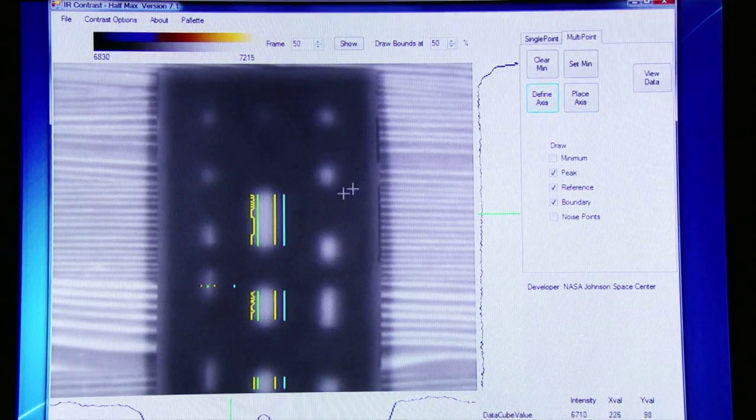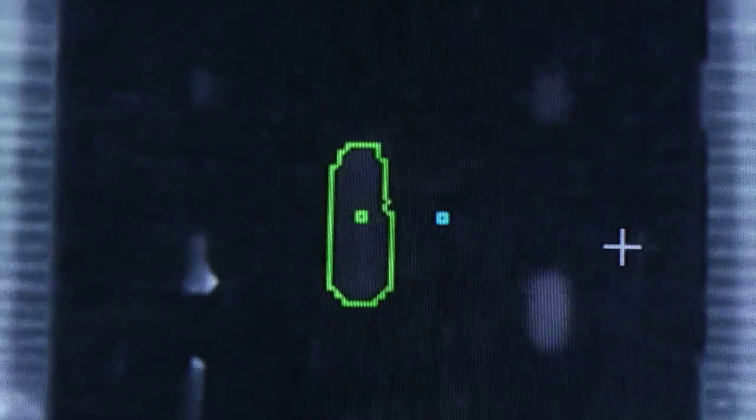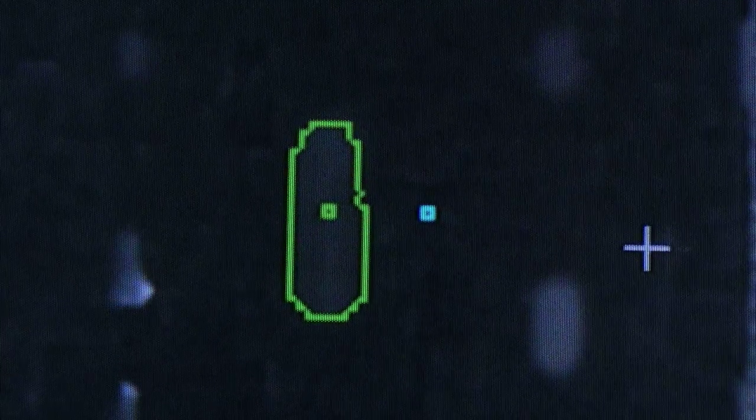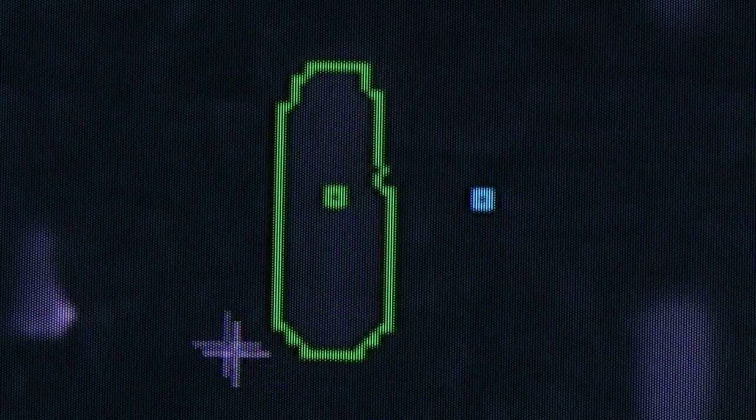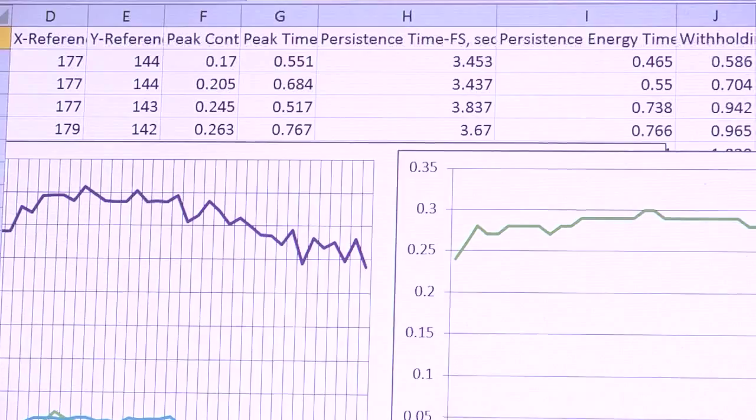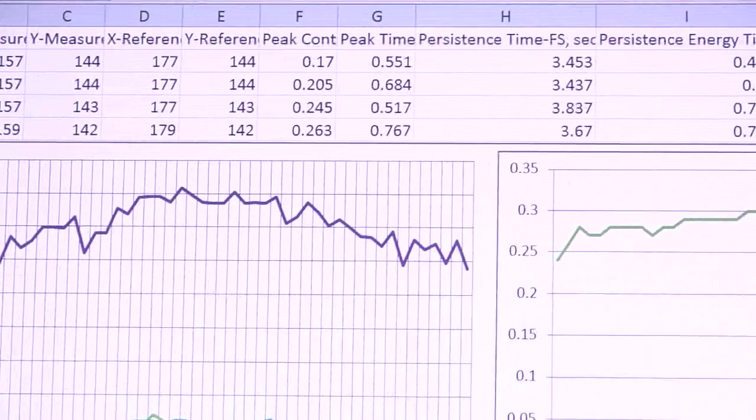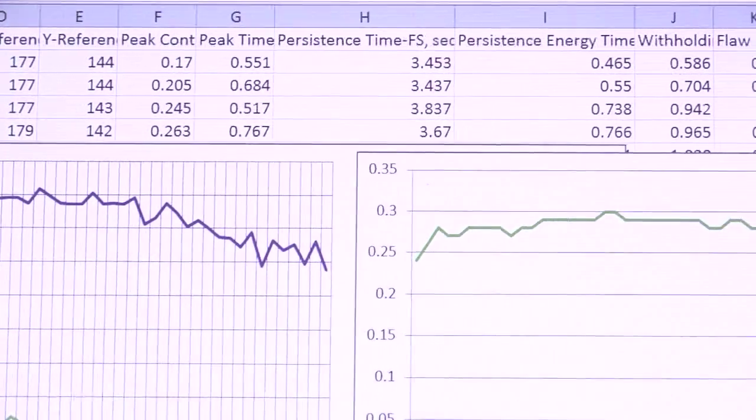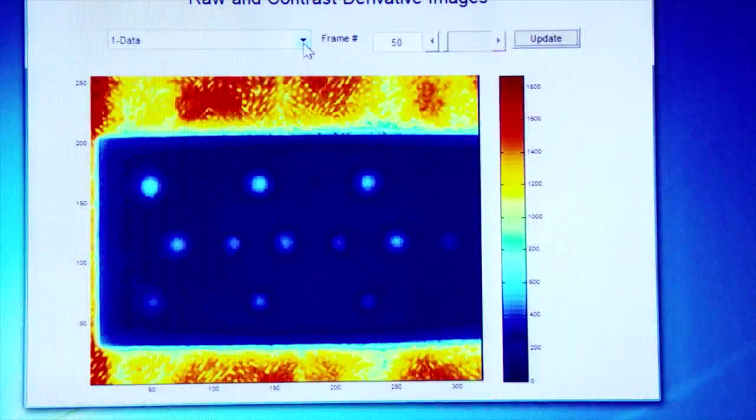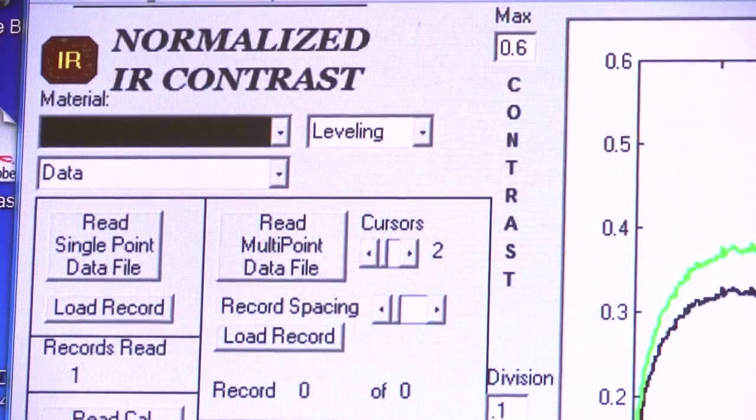This way you have a quantifiable, measurable signal response that correlates to the size of the flaw. You have a signal amplitude that can be measured very accurately, and you also have the peak of that amplitude time measured very accurately. Both of these relate to the size of the flaw as well as the depth of the flaw.